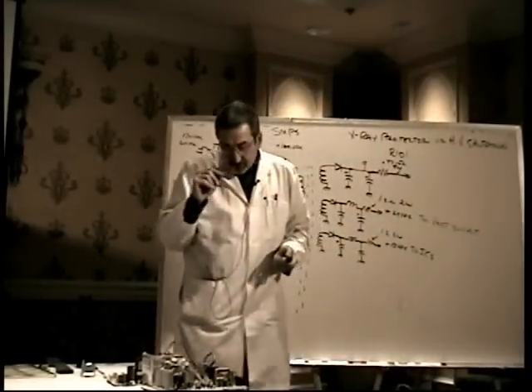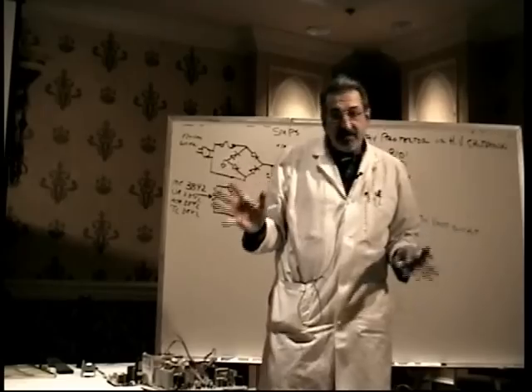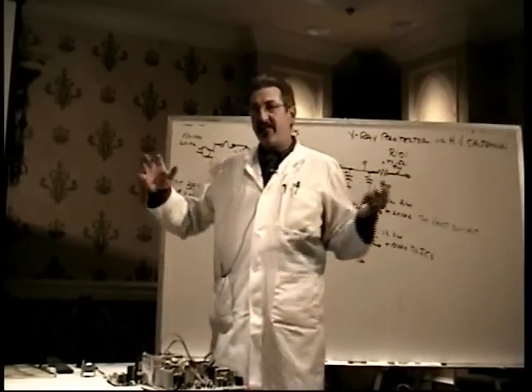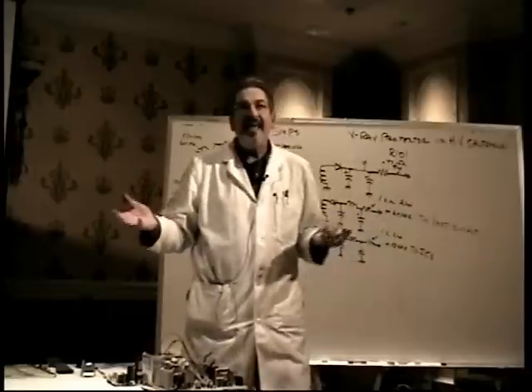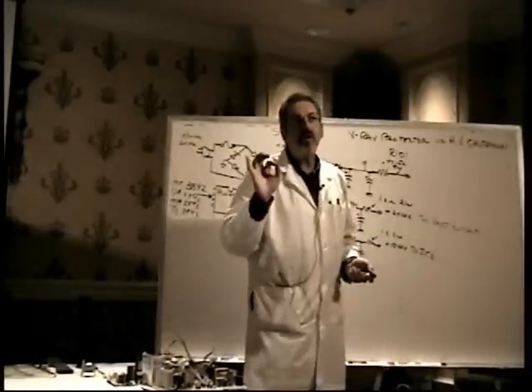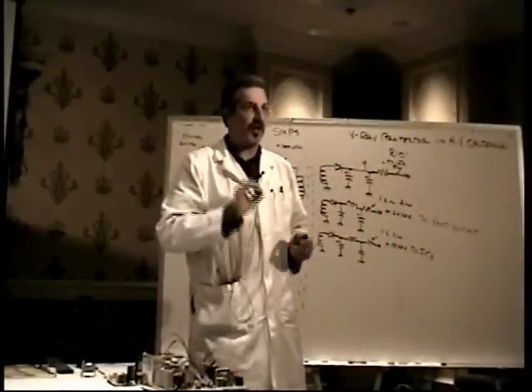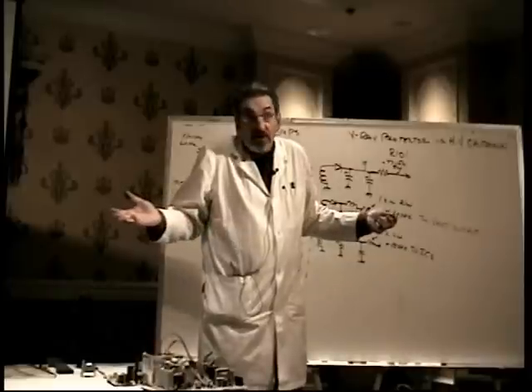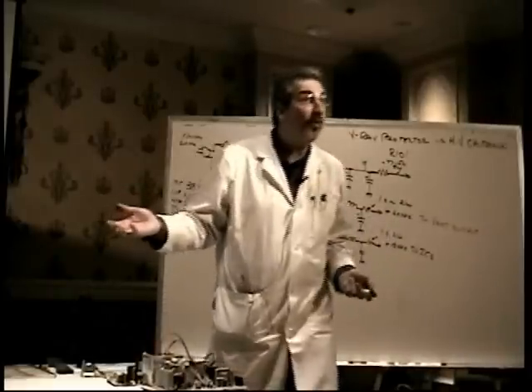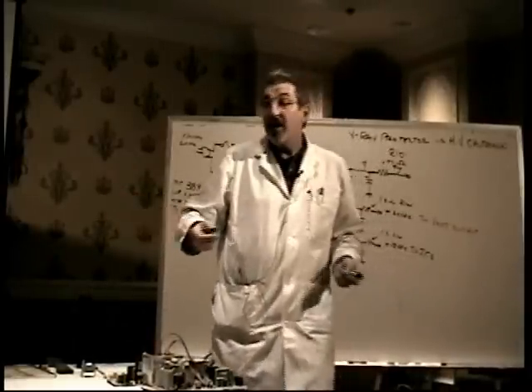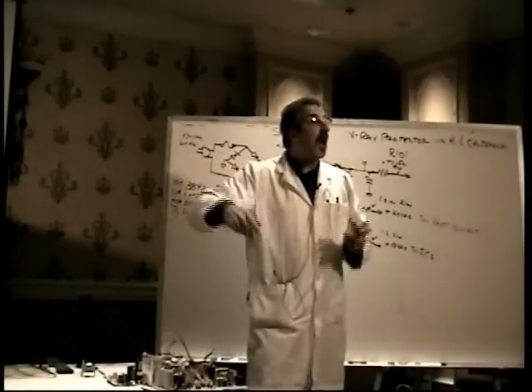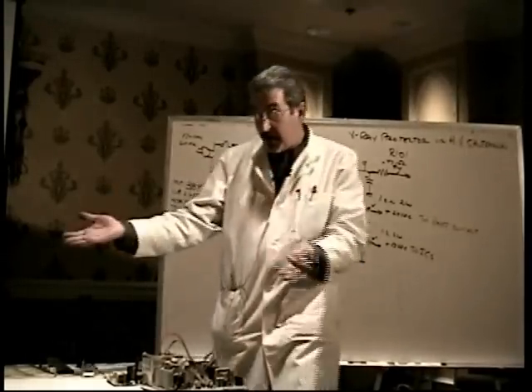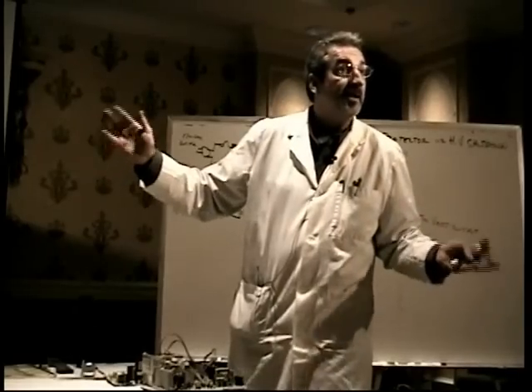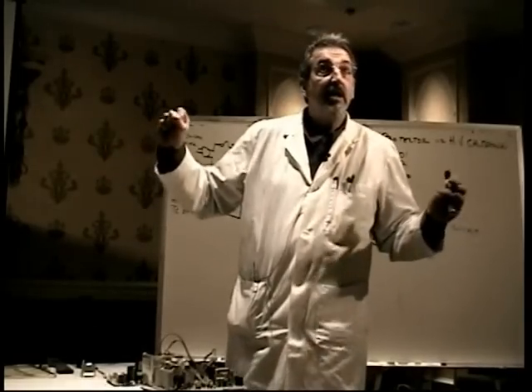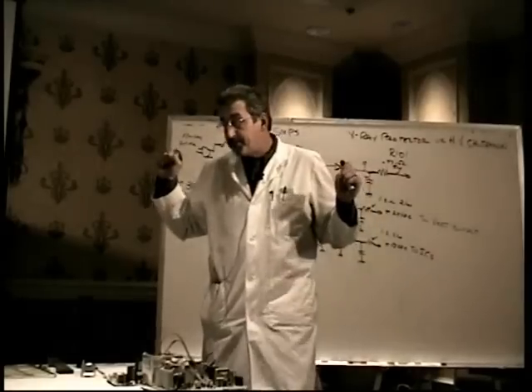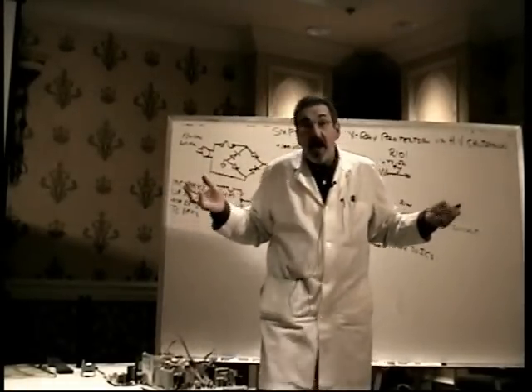And what this circuit does is, if something fails and the high voltage goes too high, it turns off the horizontal deflection circuit. Well, we know that the horizontal deflection circuit drives the high voltage, doesn't it? It drives the high voltage unit. So if I kill the horizontal deflection circuit, I kill the high voltage, and I take away the X-ray problem. Is everybody with me on that concept? Okay. So what could cause the high voltage to go too high?